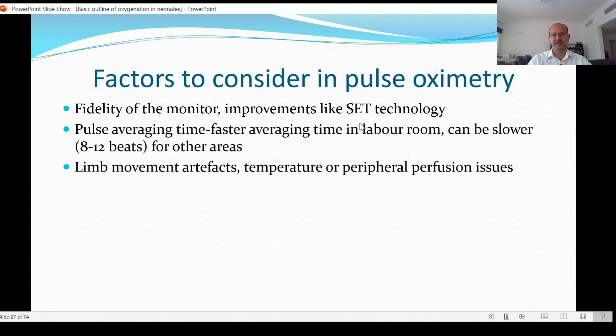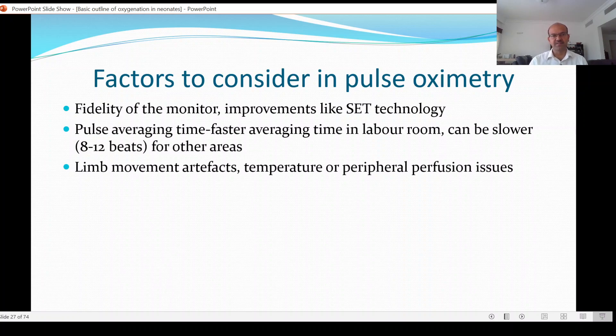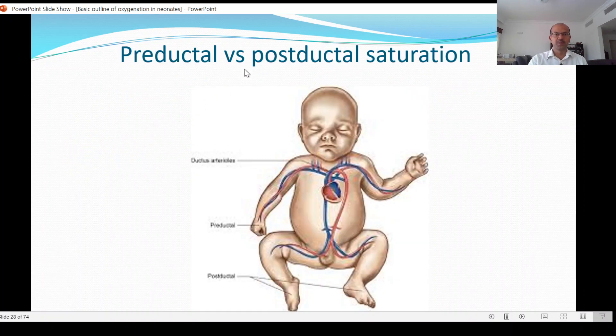Factors to consider include the fidelity of the monitor and improvements like signal extraction technology. Pulse averaging time picks up on pulsatile flow — it doesn't read for every pulse beat. With a faster averaging time, changes are more accurately reflected; you may use a faster averaging time in the labor room. Movement artifacts are reduced. Quick fluctuations may reduce with faster or slower averaging time, and limb movement artifacts, temperature, and peripheral perfusion are also important considerations.